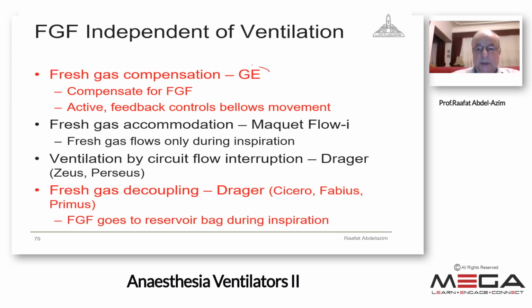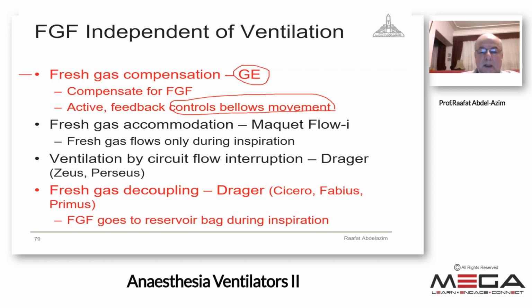In General Electric, we have something called fresh gas compensation. We'll see in the next video the effect of fresh gas compensation. What is fresh gas compensation? It compensates for changing the fresh gas flow by active feedback controls that control the bellows movement, to stop the effect of the fresh gas flow. So whenever we change the fresh gas flow, the delivered tidal volume will be approximately the preset tidal volume. In another manufacturer, Maquet Flow, they do something different.